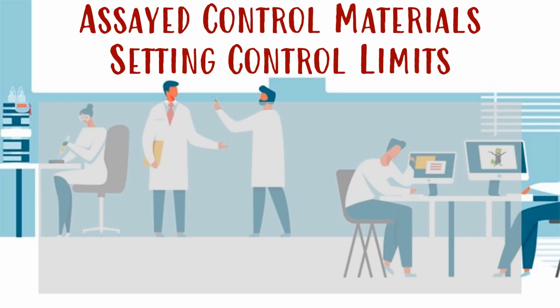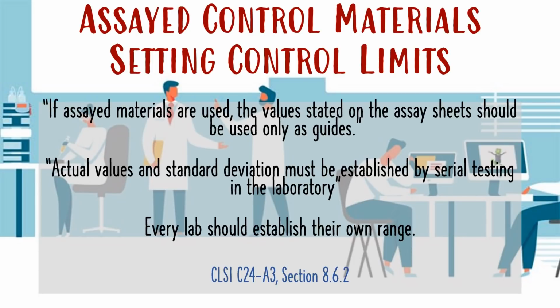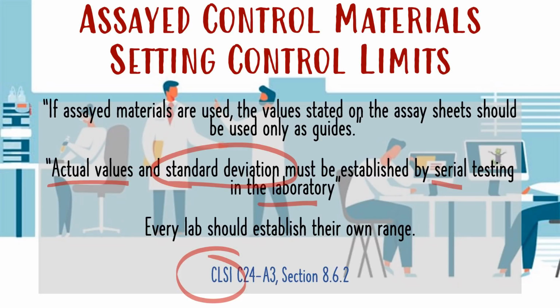So according to the Clinical Laboratory Standards Institute, okay, or what we call as your CLSI, if assayed materials are used, the values that are stated on the assay sheets, meaning in the product insert provided by the manufacturer, should only be used as guides. Okay? So, ato lang siyang reference. But somehow, in measuring the actual procedure, we are going to get the actual values and use it for computing the standard deviation. And it must be established by serial testing in the laboratory.